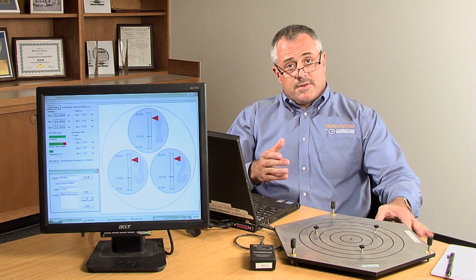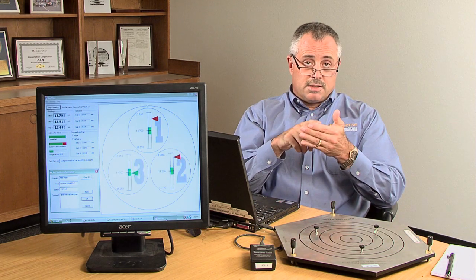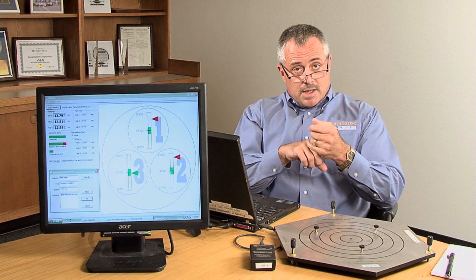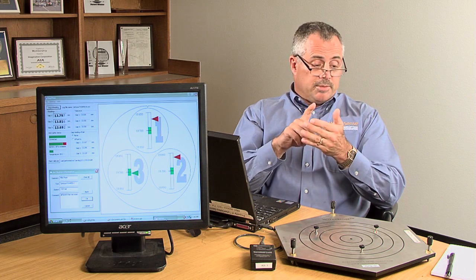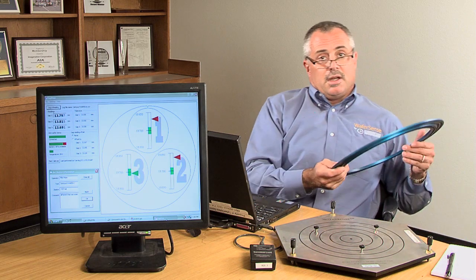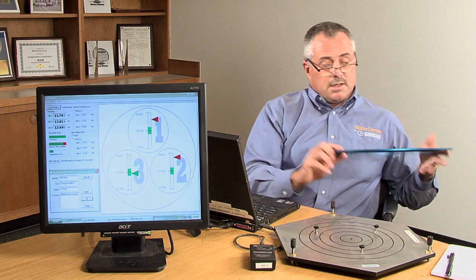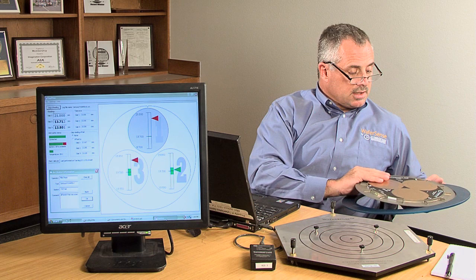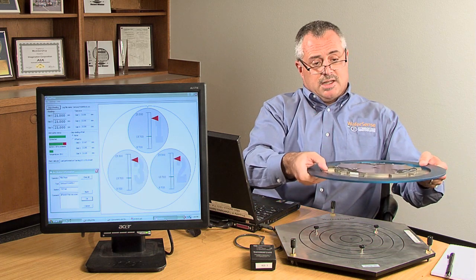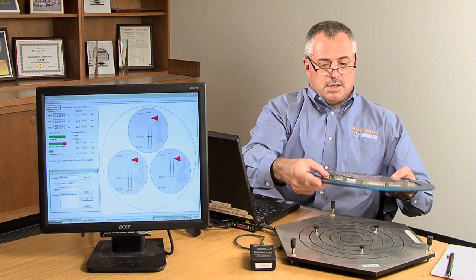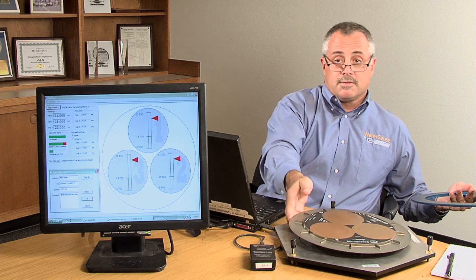The big users of AGS are typically AMAT producers, both 200 and 300 millimeter, AMAT or Novellus Vectors, 300 millimeter, and also AMAT P5000s, as well as some etch devices. In the case of Novellus Vector, an accessory that's required is a carrier ring where it's placed inside the chamber and moved throughout the chamber to each of the shower heads for gapping.